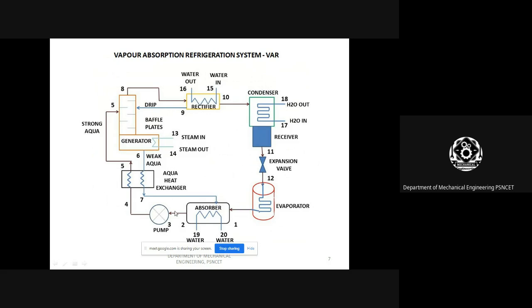Here you see, 1 to 2 is the absorber and 2 to 3 is pump work. Again 3 to 4 is pump work and 4 to 5 is a heat exchanger. This heat exchanger is used to increase the heat. That strong ammonia solution is passed on to the generator.